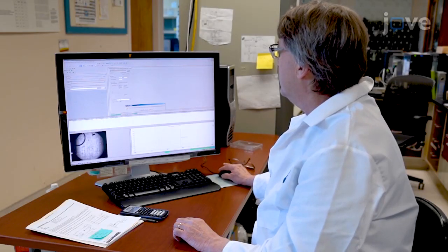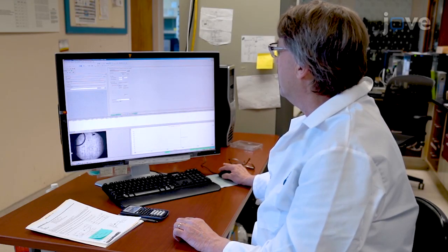Open the acquisition software and click MS Linear Mode Acquisition. For mass to charge range, enter mass to charge of the lower and upper bounds into their respective fields. Click on the sample spot to be analyzed on the MALDI target template.